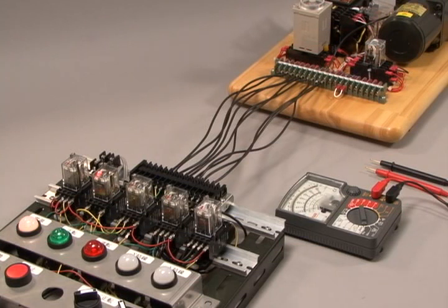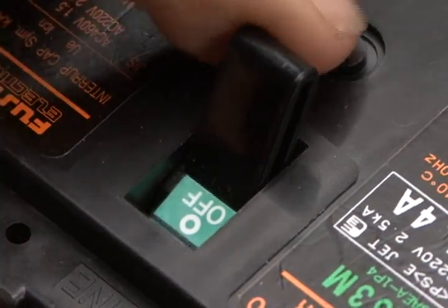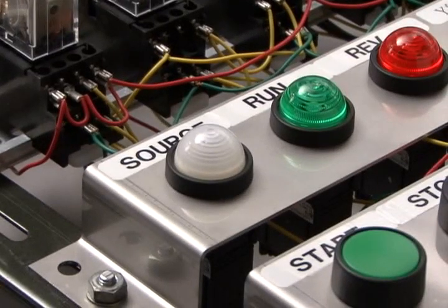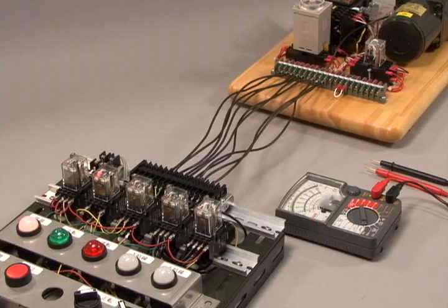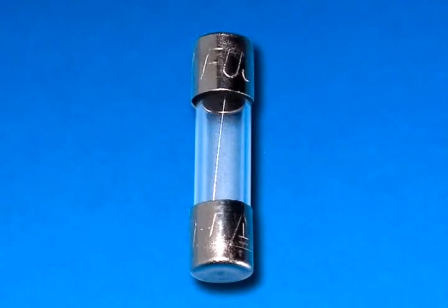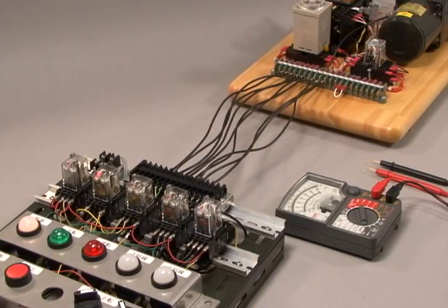Now let's think about how to locate defects with a tester using this circuit diagram. Here, let's assume a condition where the power source lamp does not illuminate, even when the MCCB is turned on. First, let's check the fuse. You can usually determine the state of a glass tube fuse by looking at it. If visual confirmation is not possible or is inconclusive, voltage can be measured at the output side of the fuse. Even if only one fuse is blown, voltage at the output side will be 0.